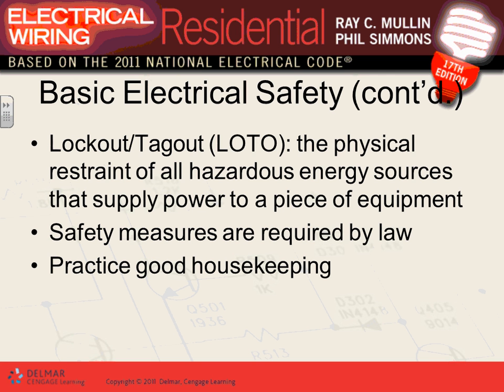The rule has an exception: working on energized equipment. The only time you are allowed to work on things energized is under two conditions. Condition number one: you cannot troubleshoot this equipment unless it's energized. Like a magnetic starter, you can't troubleshoot a magnetic starter unless you energize it. That's rule number one. Number two, if de-energizing the object will create more hazard.